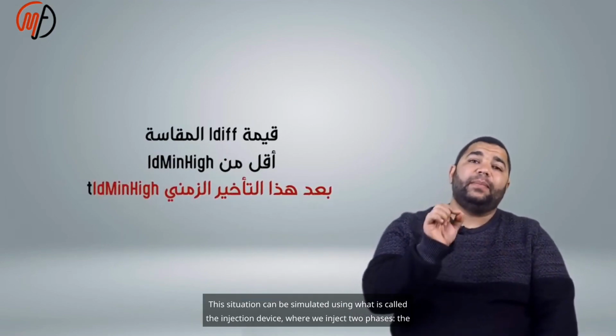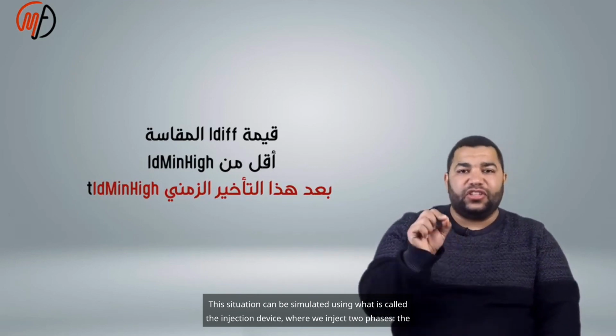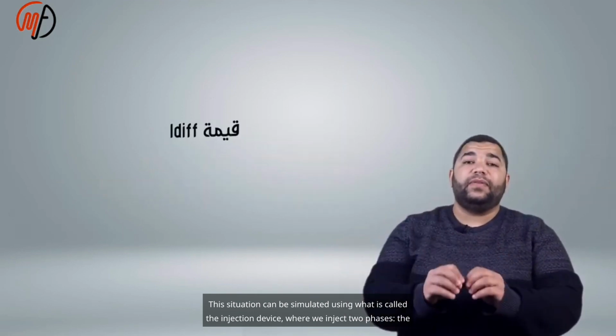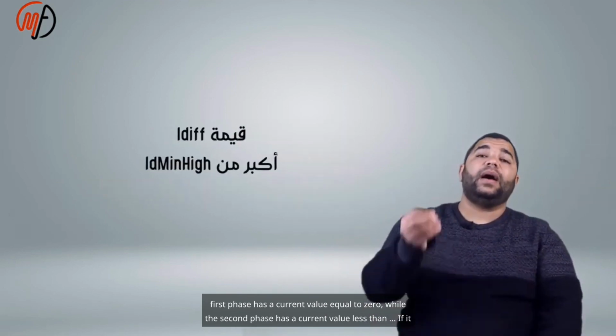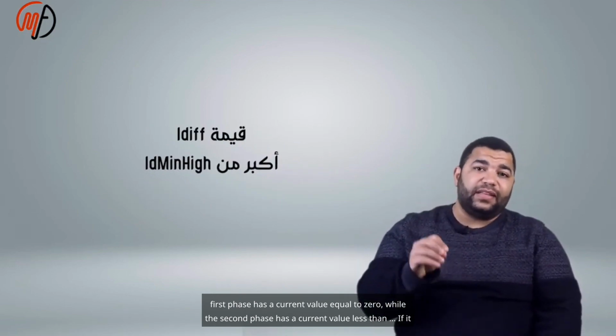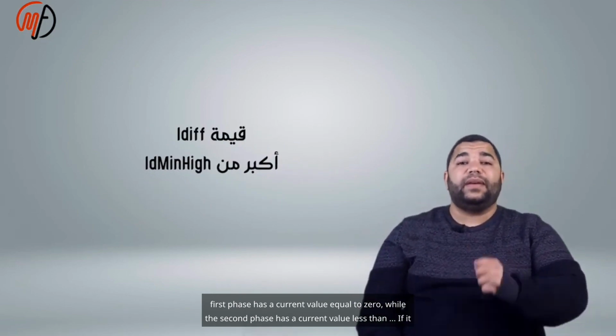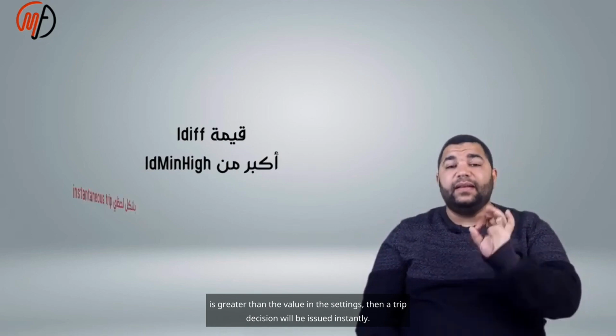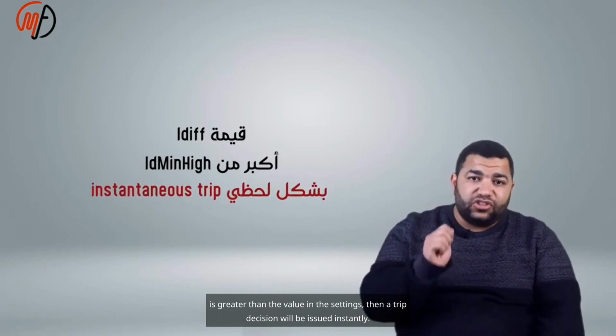This situation can be simulated using what is called the injection device, where we inject two phases. The first phase has a current value equal to 0, while the second phase has a current value less than. If it is greater than the value in the settings, then a trip decision will be issued instantly.